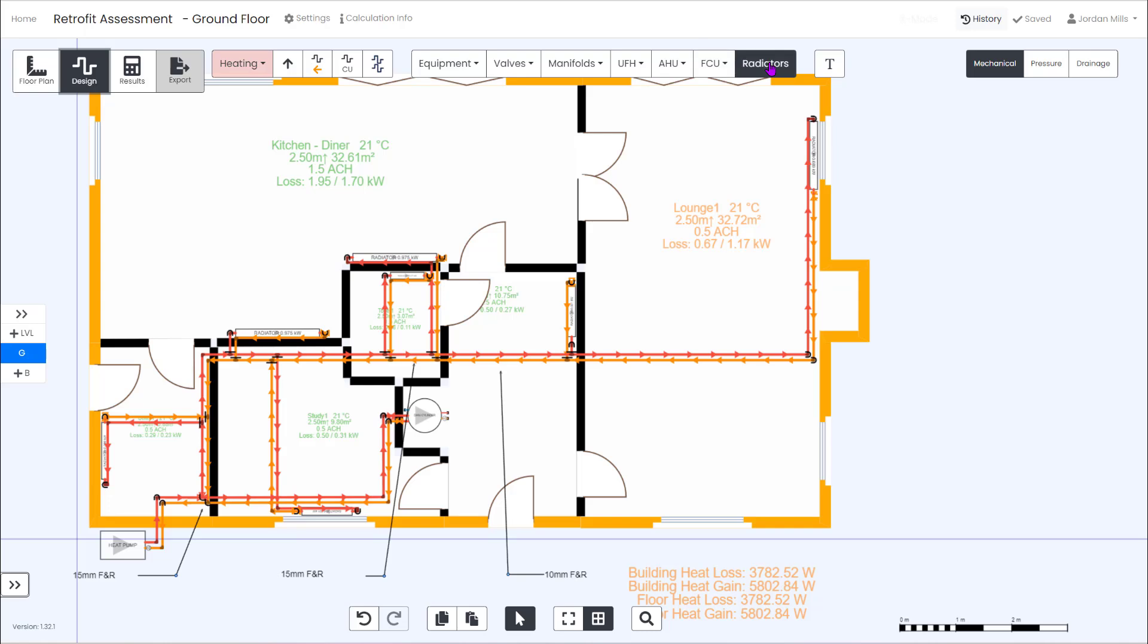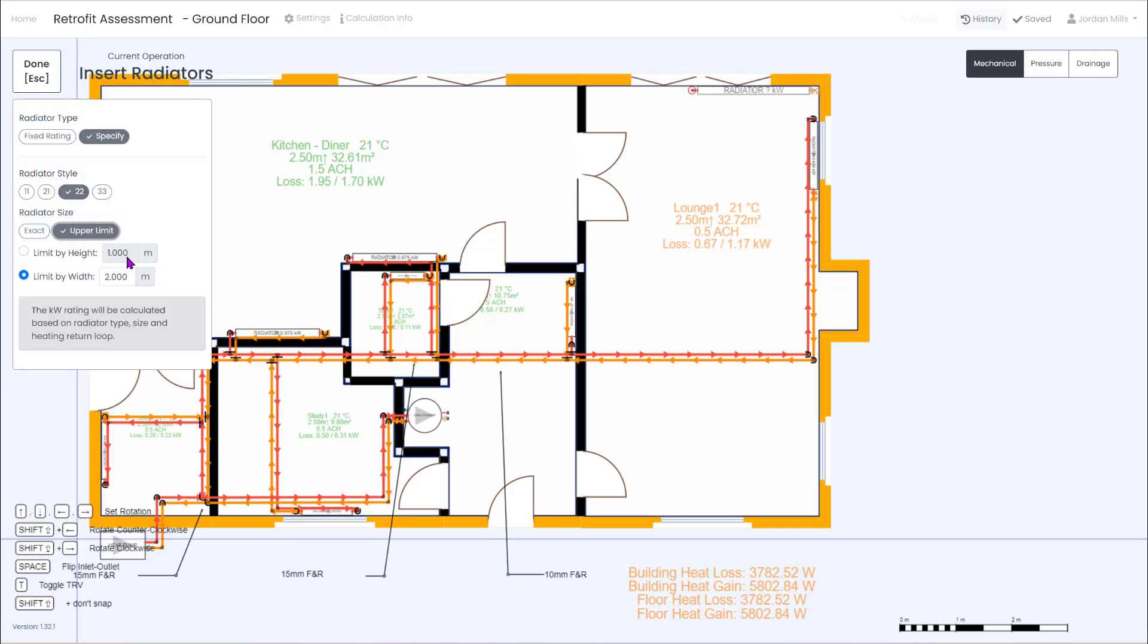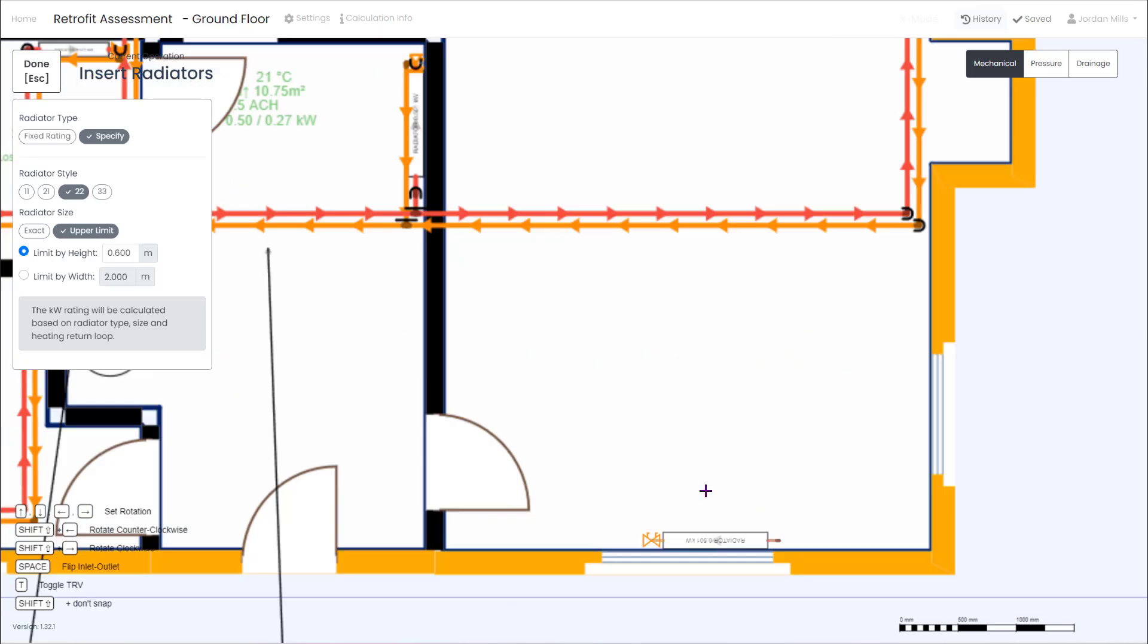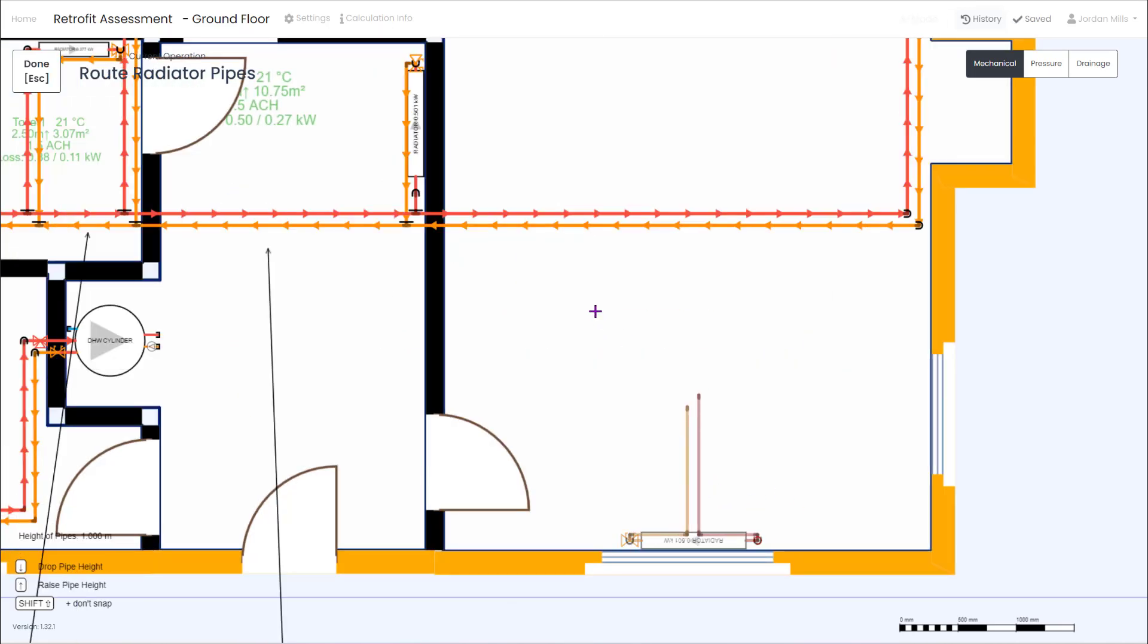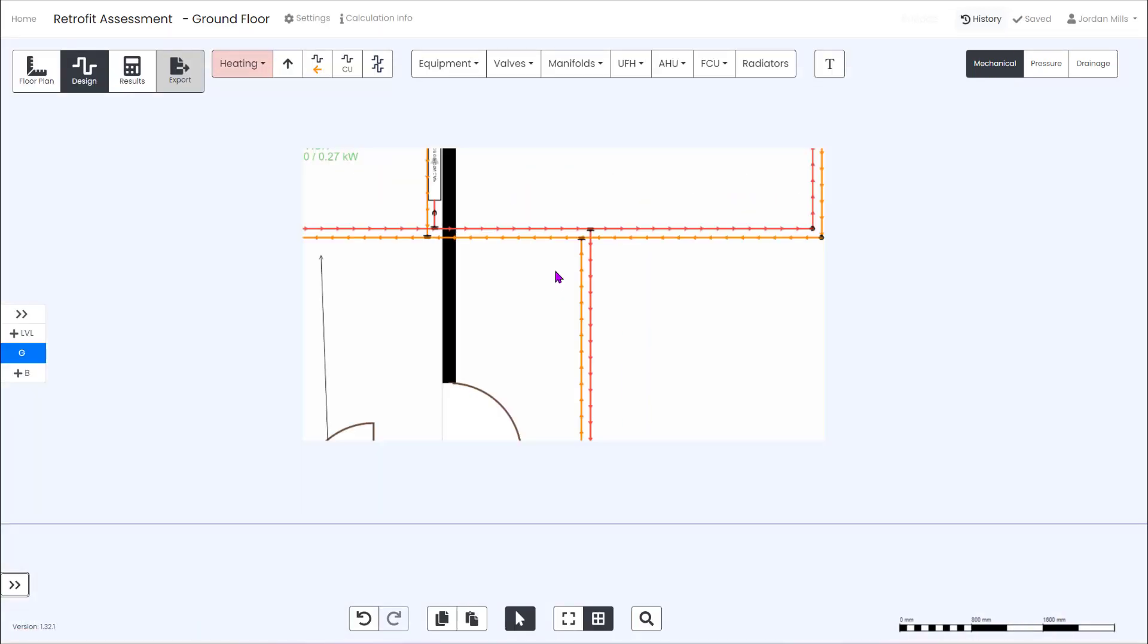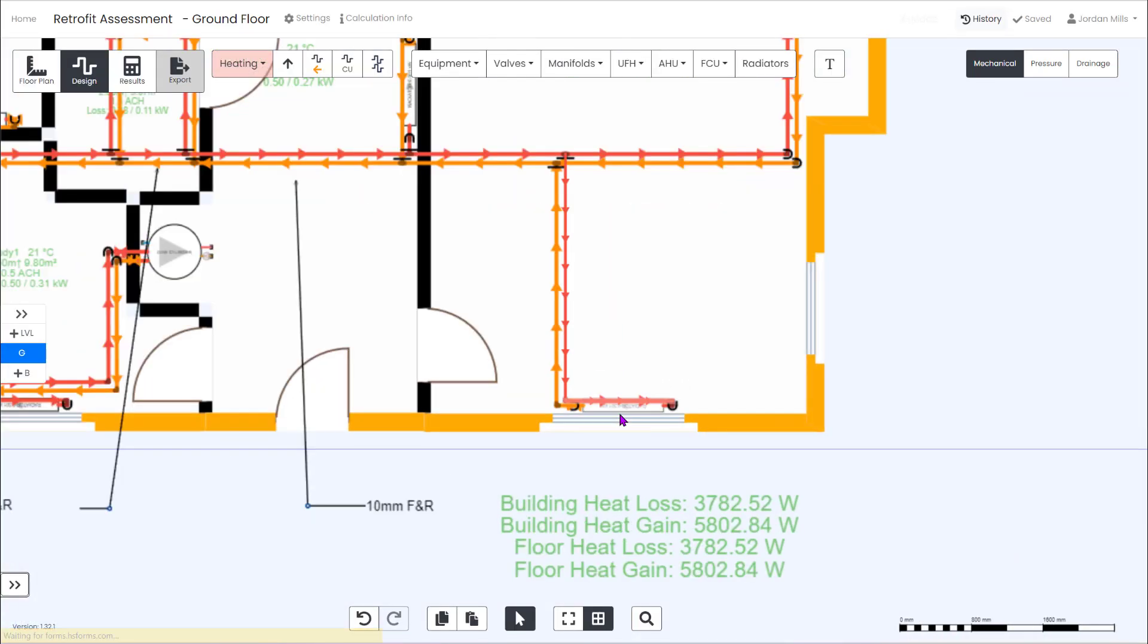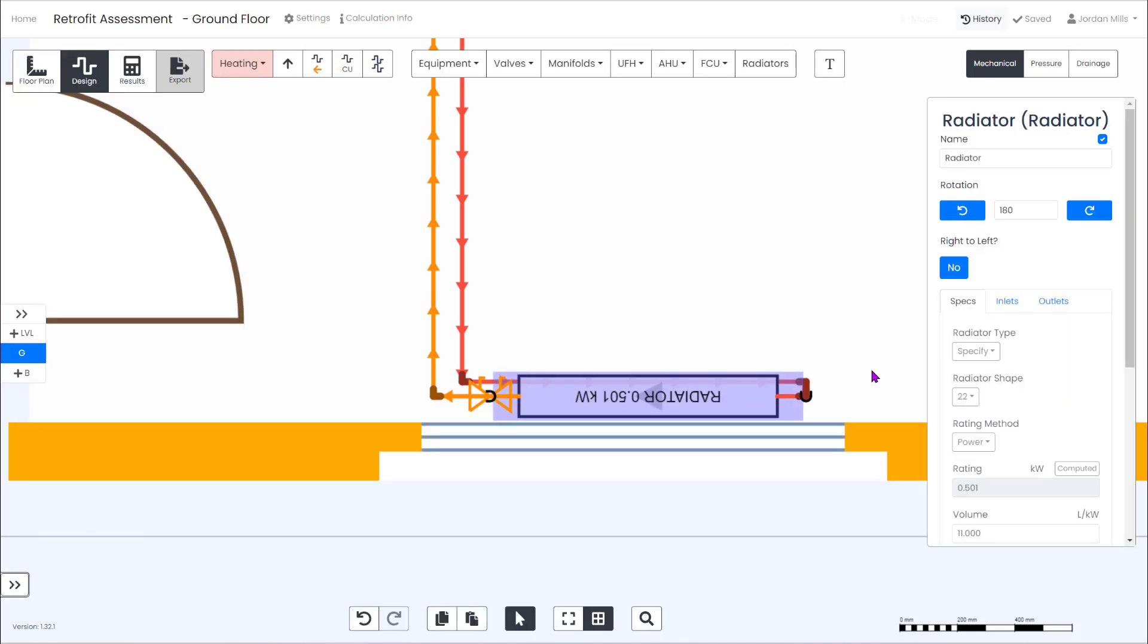So we can go ahead and add that. If you specify a radiator type and a maximum dimension such as 600 high, H2X will calculate the required width to satisfy the heat load based on the room design temperature and the flow temperature from the heat pump. So a type 22 at 600 high will need to be 900 wide to produce the required 500 watts at a DT20.